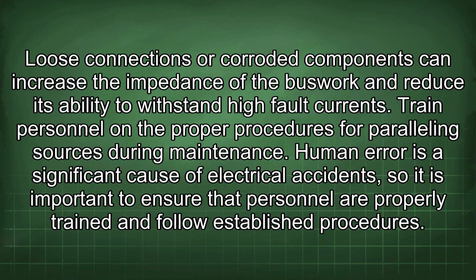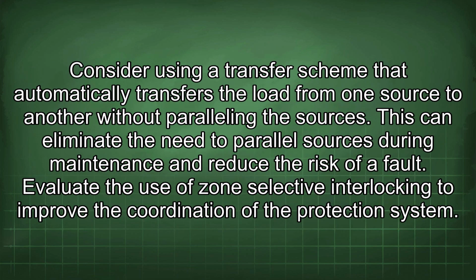Human error is a significant cause of electrical accidents, so it is important to ensure that personnel are properly trained and follow established procedures. Consider using a transfer scheme that automatically transfers the load from one source to another without paralleling the sources. This can eliminate the need to parallel sources during maintenance and reduce the risk of a fault.